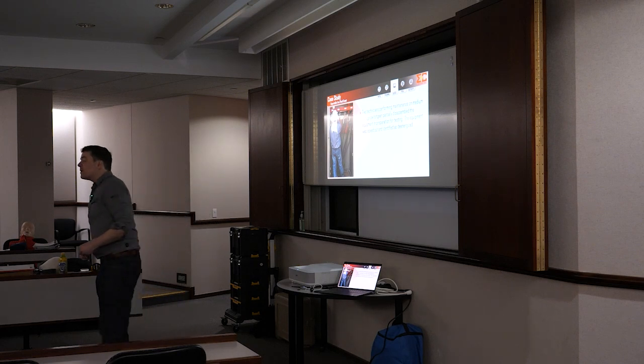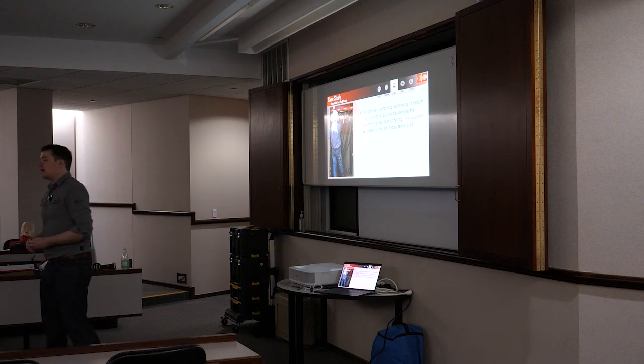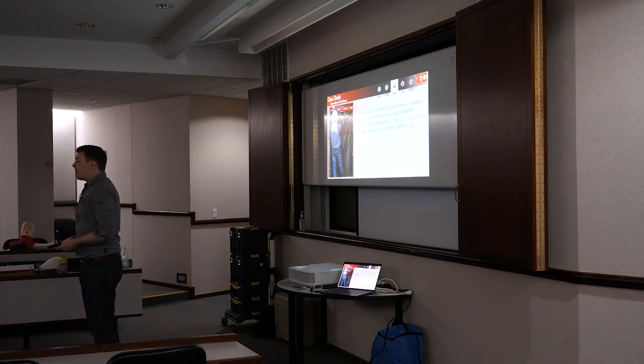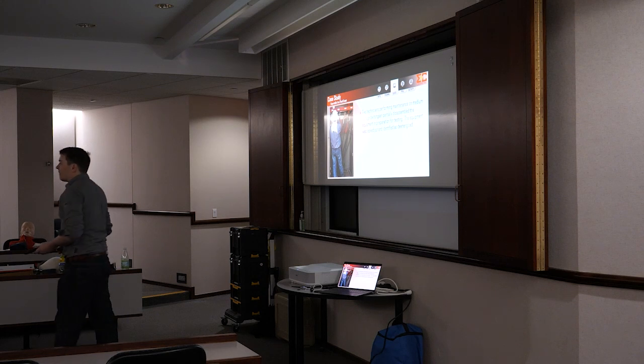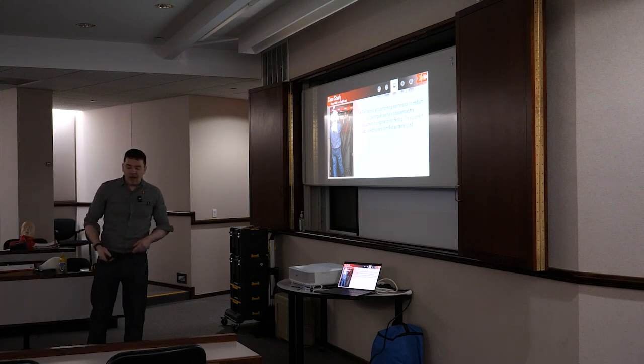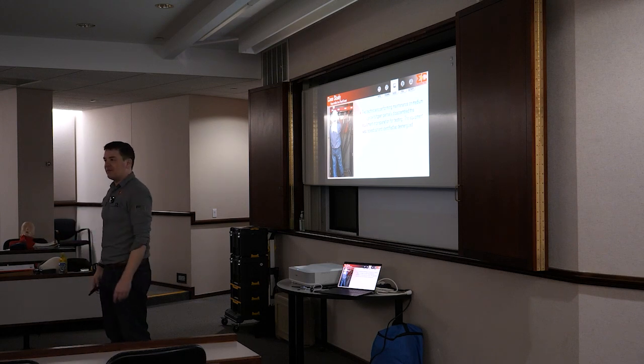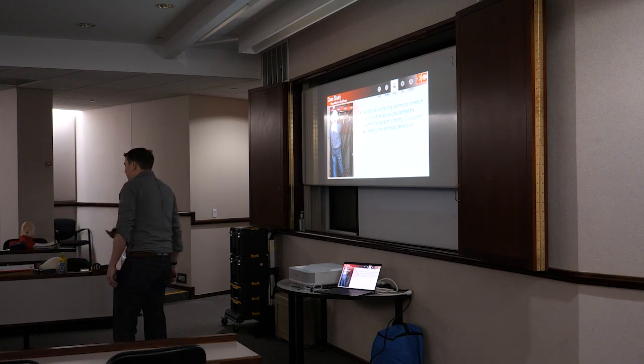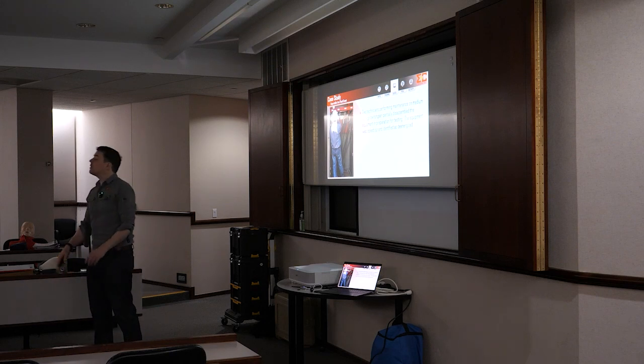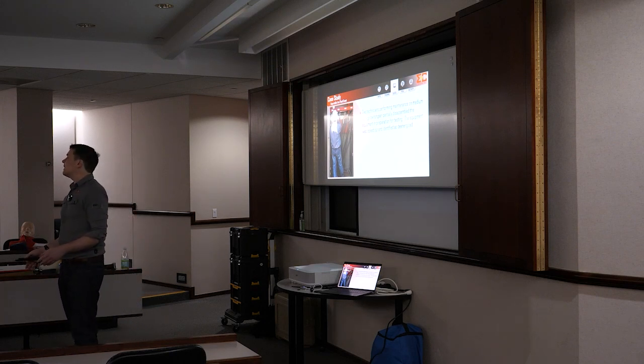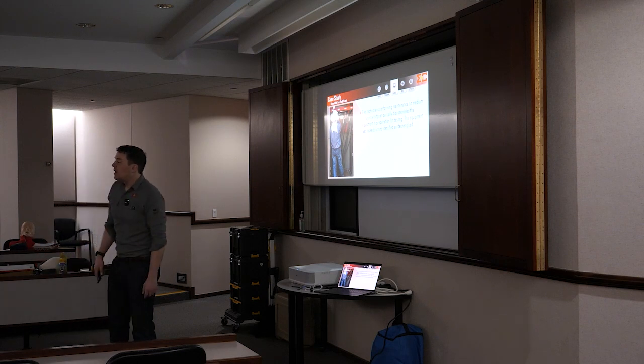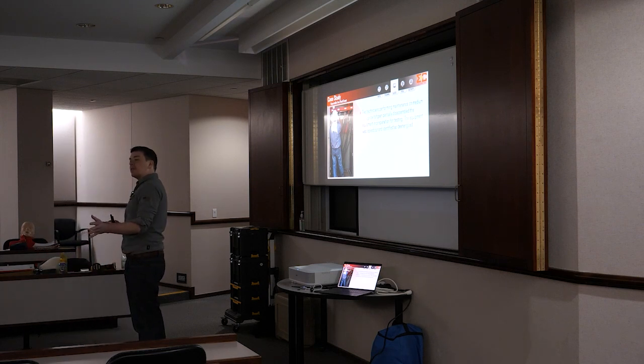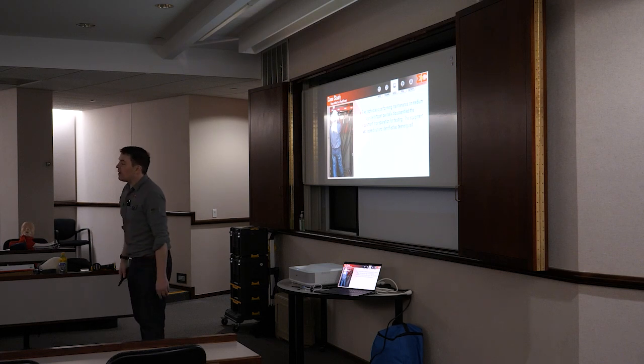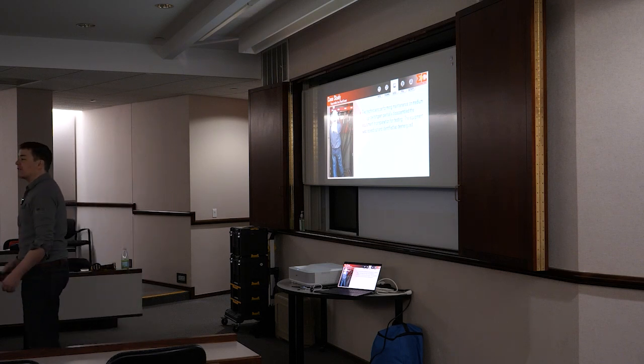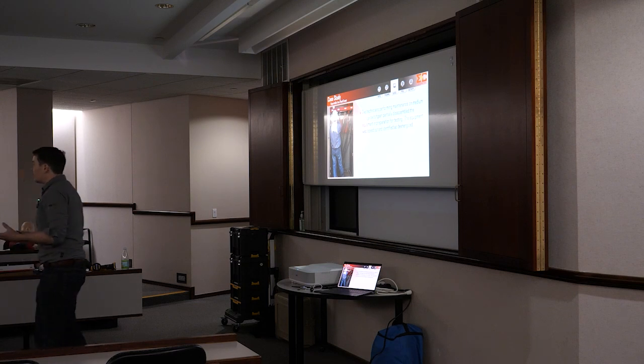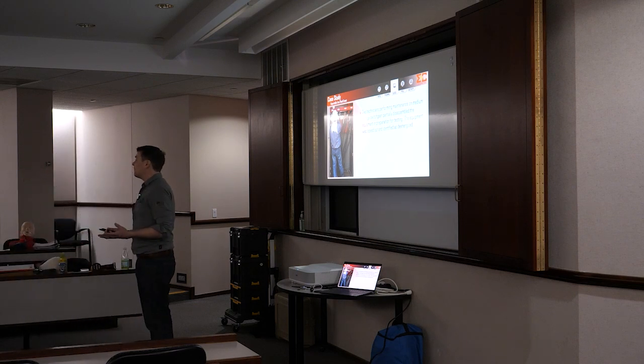The ultimate reason for the flash, as I found working on the incident analysis with them, was that it happened to be a relatively humid and dewy morning after a cool night. There was a lot of condensing humidity, and this switch hadn't been serviced in years and years. There were a large number of cobwebs in there. Normally those cobwebs aren't a problem because there's relatively limited airflow in some of this equipment, but the fact that Bob and George had just taken off one of the covers was enough to induce a draft inside. A moisture-laden piece of cobweb went across the medium voltage bus we had in there and immediately flashed.